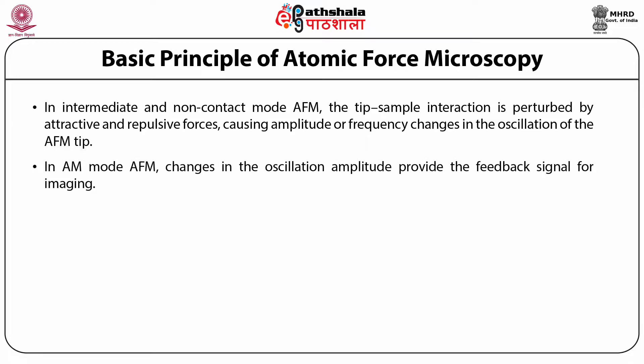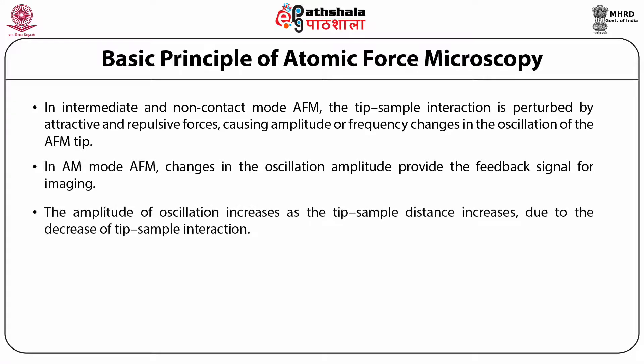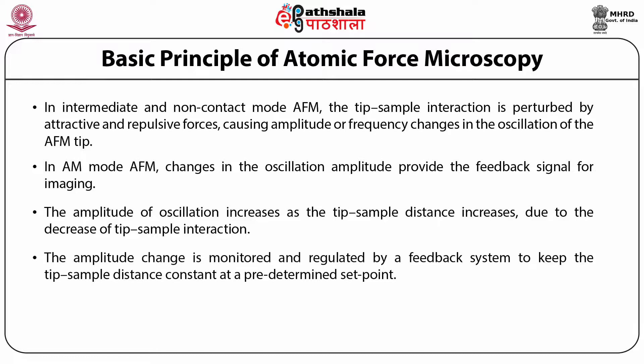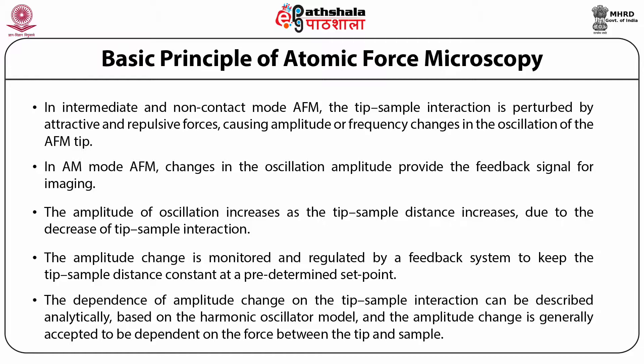In AM mode AFM, changes in the oscillation amplitude provide the feedback signal for imaging. The amplitude of oscillation increases as the tip-sample distance increases due to the decrease in tip-sample interaction. The amplitude change is monitored and regulated by a feedback system to keep the tip-sample distance constant at a predetermined set point. The dependence of amplitude change on the tip-sample interaction is described analytically based on the harmonic oscillator model, and AM mode measurements represent the direct force between the tip and the sample.